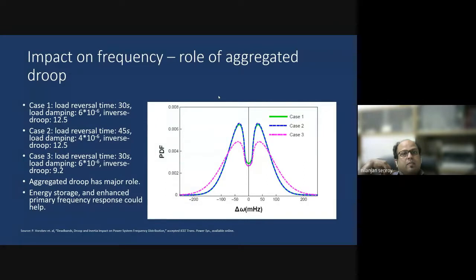Similarly, when you have primary frequency control enabled in different generators, you may have the droop, 3%, 4% droop that you may have enabled. The higher the droop, 5% droop, means the generator is reluctant to take part. 2% droop means the generator is extremely willing and capable to take part in the frequency control. So the droop also has a major role to play in the shape of this bimodal distribution.